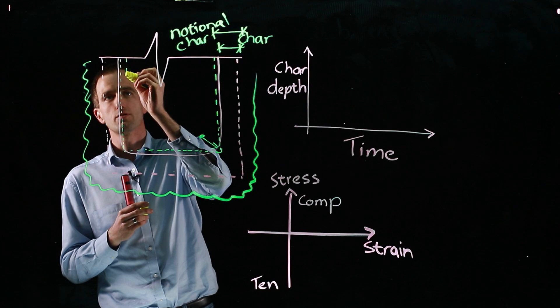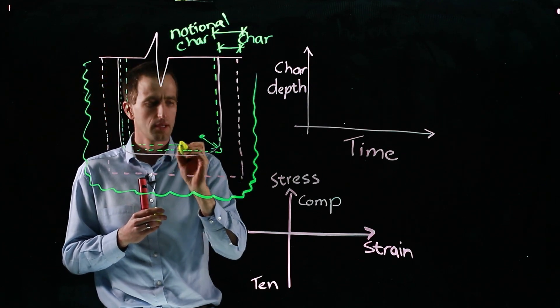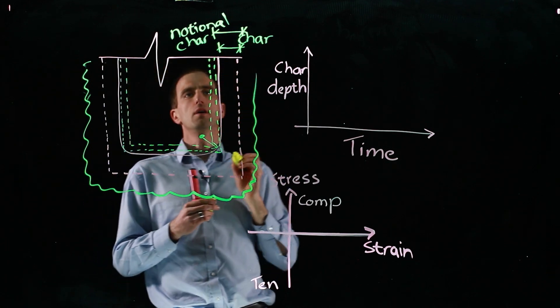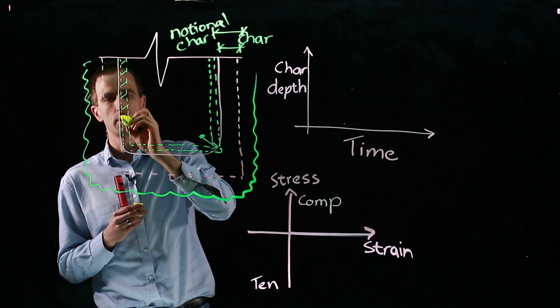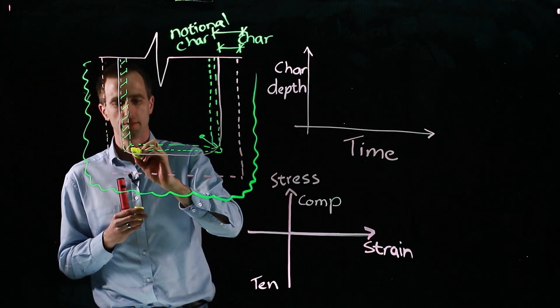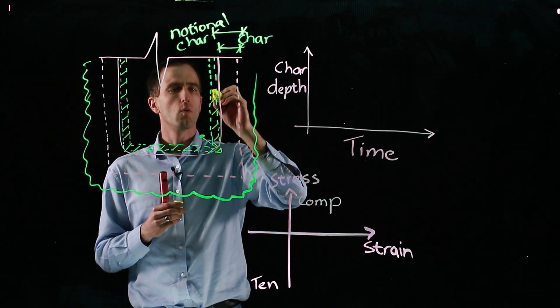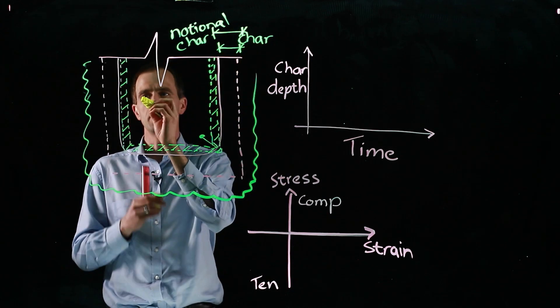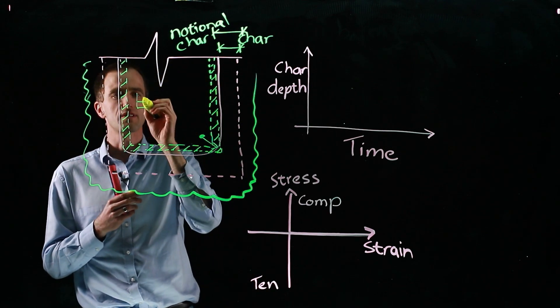So then what we have to do is reduce the section further like that. And we lose another bit of material. And the Eurocode recommends about seven millimeters for this area of zero strength, which we can't rely on. And once we've reduced it by the notional charring plus this extra bit of heated material, then we have an effective section.